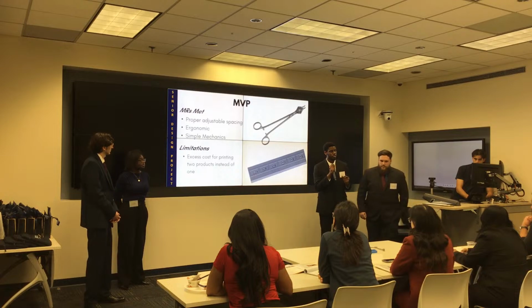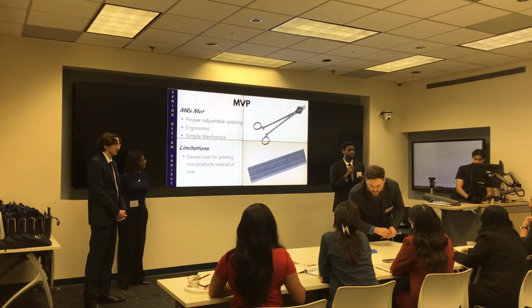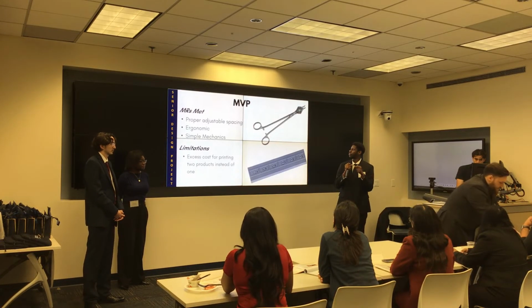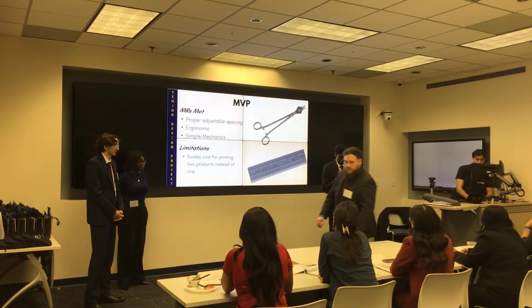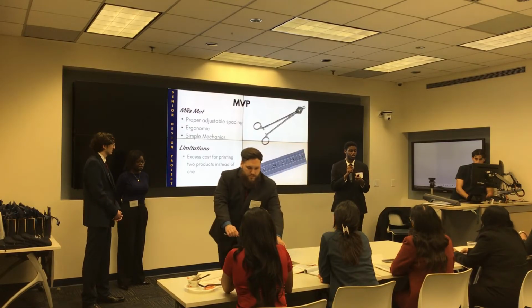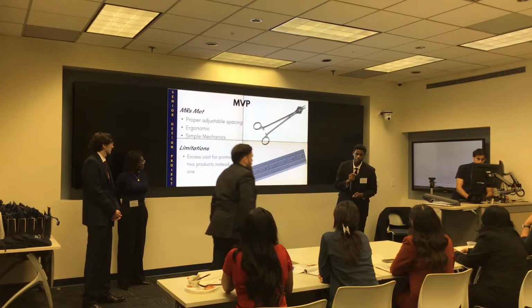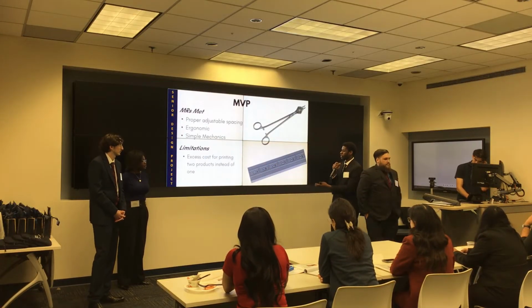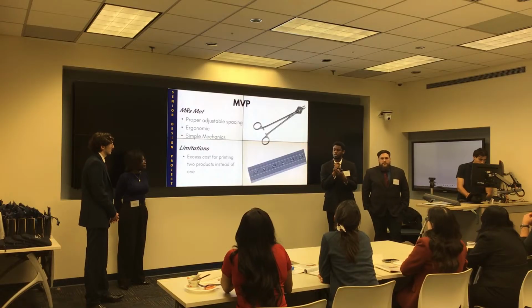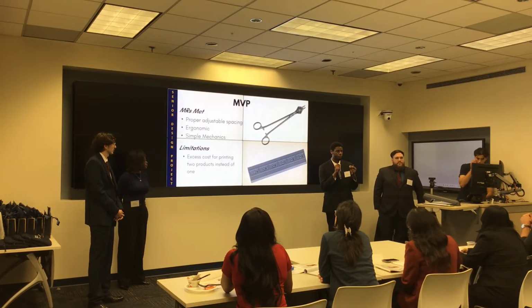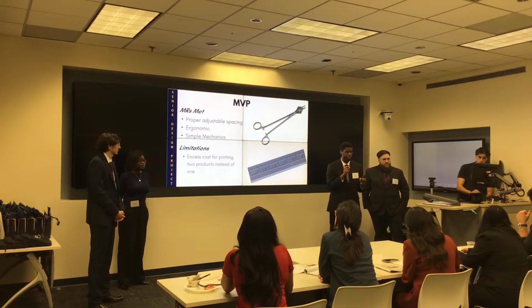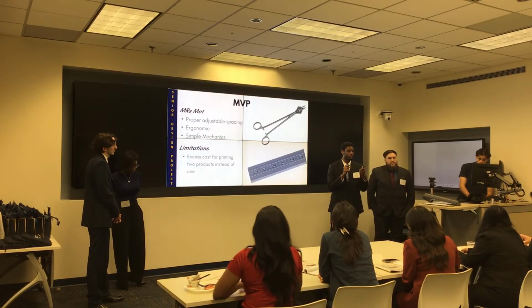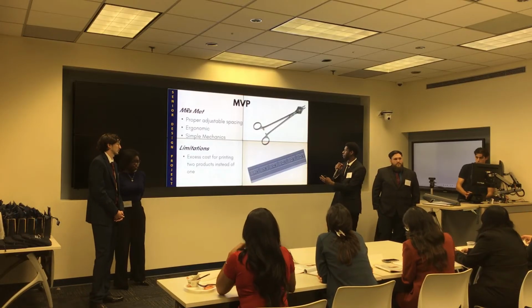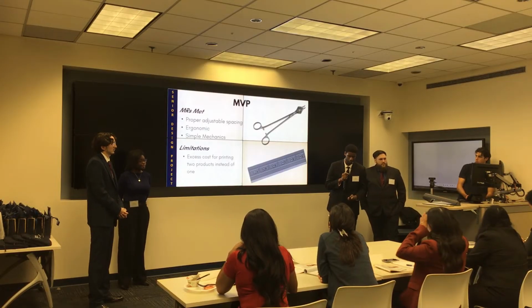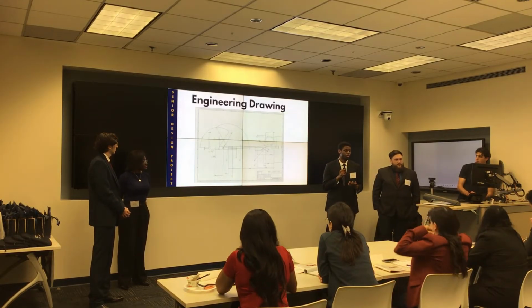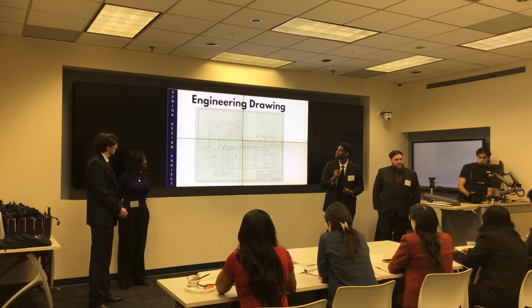We decided to go with the scissor-like surgical design. This is a design that surgeons are very familiar with for our dual vessel clip applicator in order to grab and place two vessel clips simultaneously onto the vessel. We also finalized the design of what we call a clip cradle. This is the precision component that would allow for the proper alignment, consistent and accurate placement of the vessel clips onto the vessel at the proper millimeters that the surgeon requires it to be placed at. Here's the engineering drawing of our dual vessel clip applicator, as you can see.